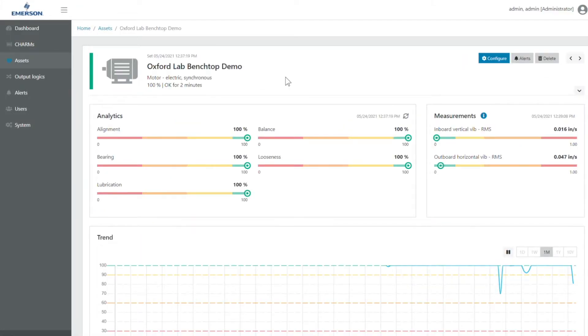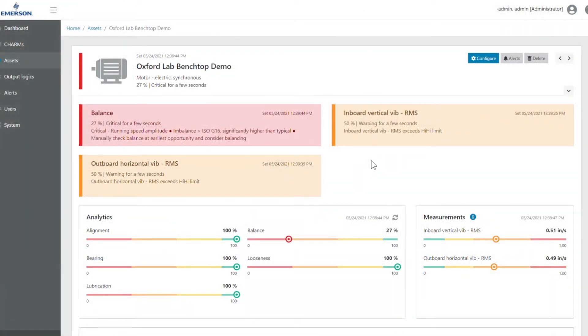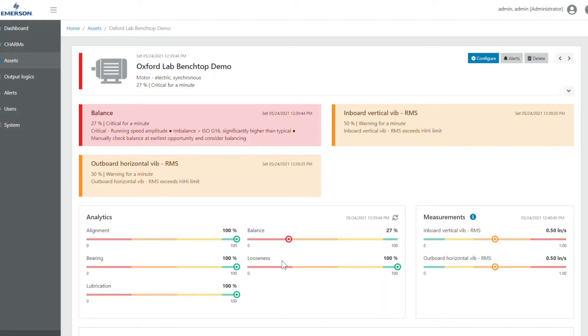Currently the motor is not running so no asset health issues are shown. Underneath each asset we can see which individual factors are affecting overall machine health based on the analytics shown on the left and the machine measurements shown on the right. Now let's see what happens when we turn the motor on. The health score of our asset dropped and changed from green to red indicating a critical issue. Both vibration sensors are showing elevated readings. The onboard analytics have determined the issue to be a problem with balance. The other analytics enabled for this asset are green with a health score at or near 100%, indicating no issues with alignment, bearing fault, lubrication, or structural looseness.